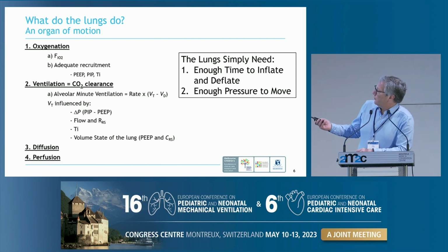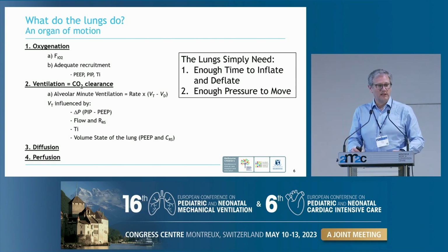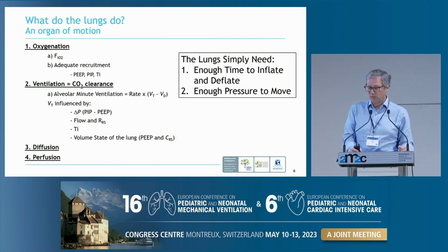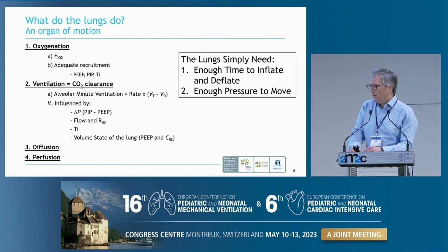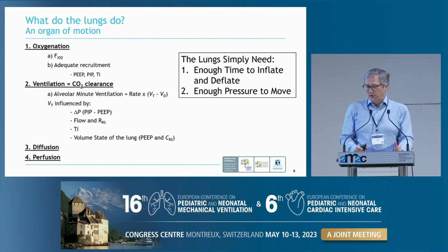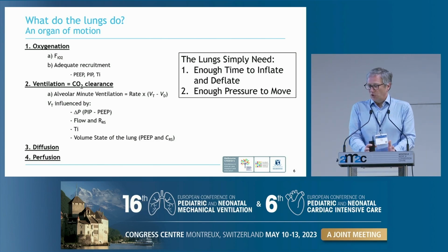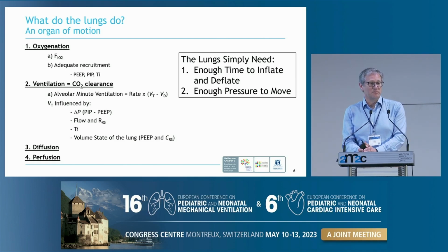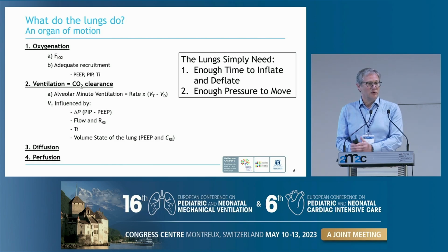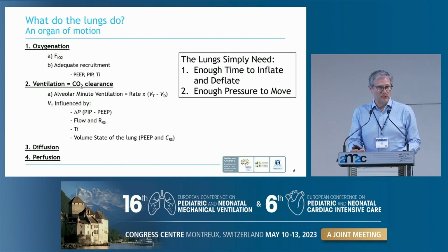We can use our ventilator to control oxygenation and ventilation, and you can see here the ways we can do that are exactly the same in an adult, a paediatric and a neonatal lung. The concepts are the same. What we need to do is to give the lung enough time to inflate and enough time to deflate and apply only enough pressure to make it move as much as you need it and not make it move more than you need it.